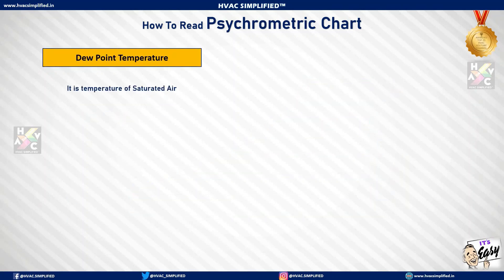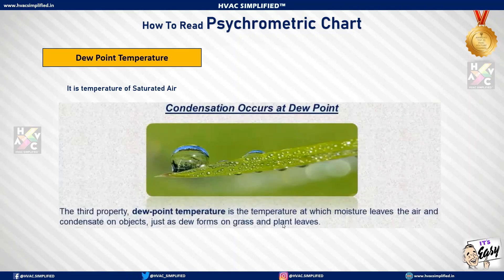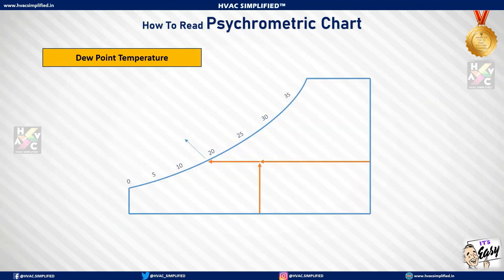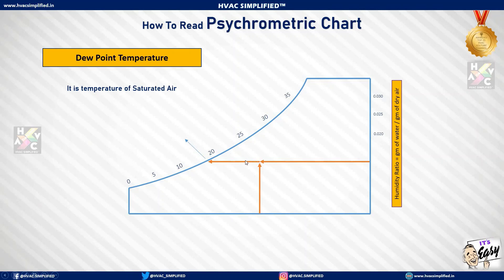Dew point temperature is the temperature of saturated air — the temperature at which moisture leaves the air and condenses on objects, just as dew forms on grass or plant leaves. It represents the maximum amount of water vapor that air can hold at a given temperature. On the psychrometric chart, dew point temperature is read on the left-hand side, where the dry bulb and wet bulb temperatures become the same.